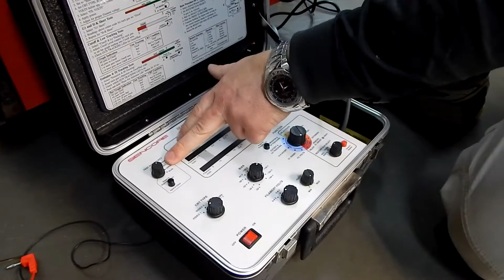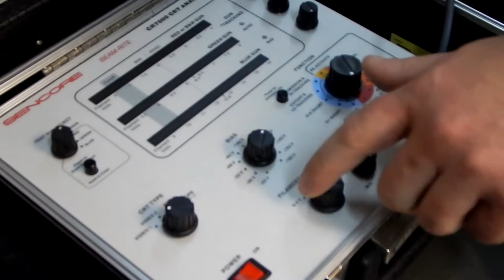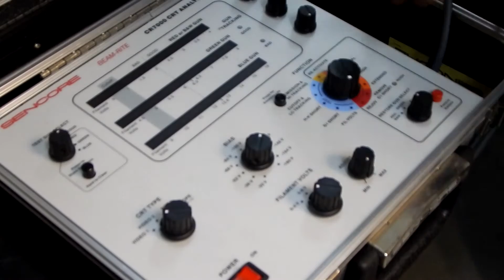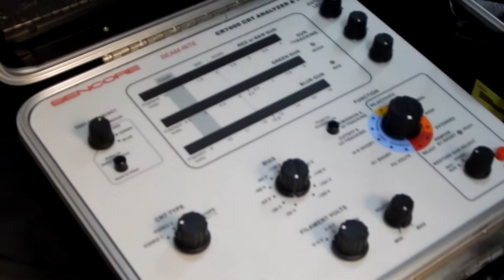On our equipment here, we have the test guns. We can either do red, green or blue or simultaneous. We have the CRT type, power switch, filament volts, the bias, your adjustment for the filament volts, and we've got various controls here for when we're doing our test. So what I'll do first is I'll switch everything to their base levels, and then we'll have a look at the manual again.